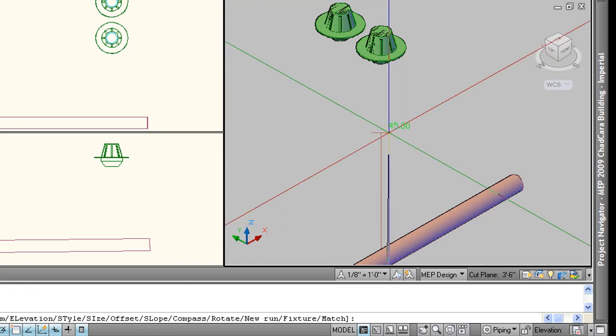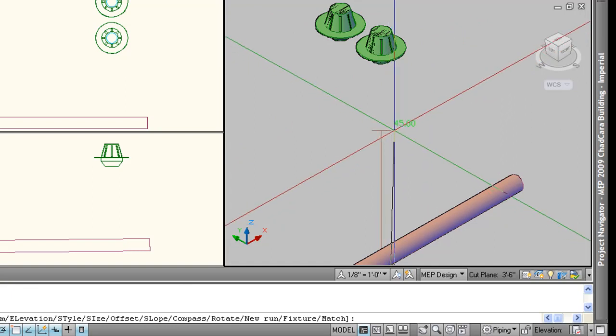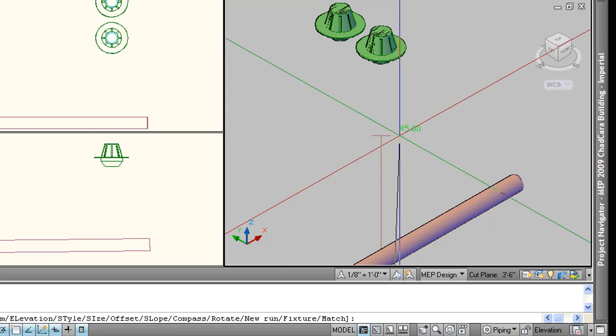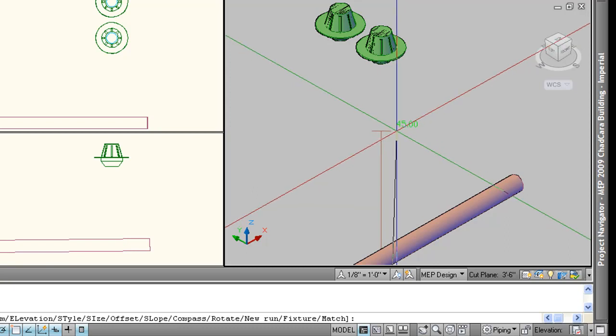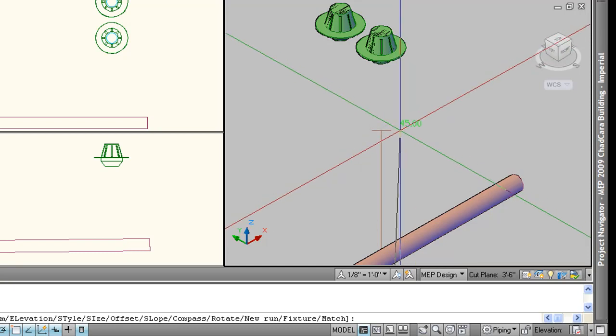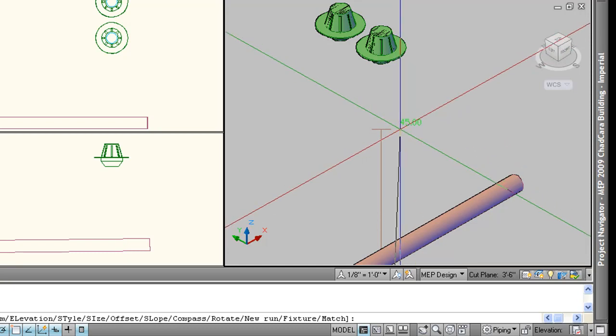But this time I didn't get that. I didn't get what I was expecting here. And you're going to run into this, which is why I'm showing this to you. What did I get here? This funny line that I'm getting is what's called a plumbing line. In AutoCAD MEP there are two types of pipes that you can draft in. You can draft in plumbing lines or piping lines, in 2D entities or three-dimensional solids. So what I have here is a plumbing line. It's a 2D flat line on a page to depict a plumbing or pipe line.